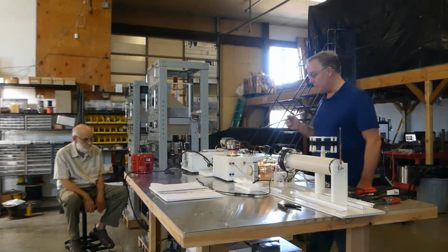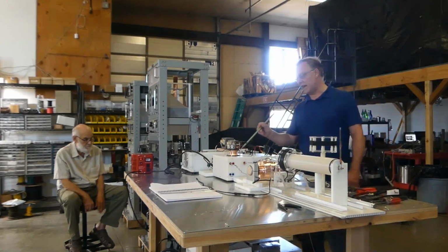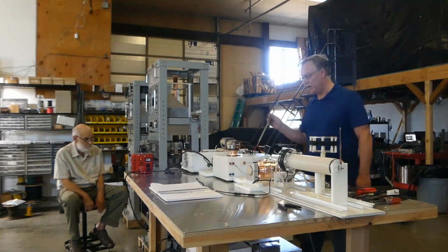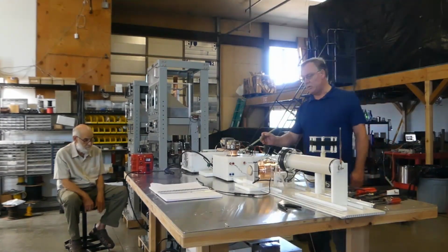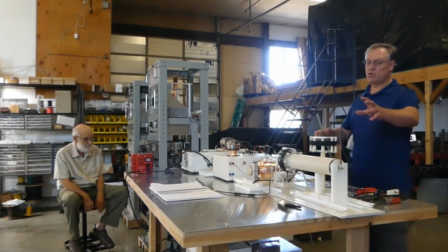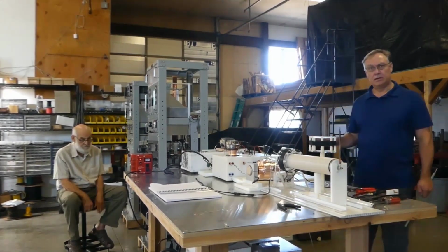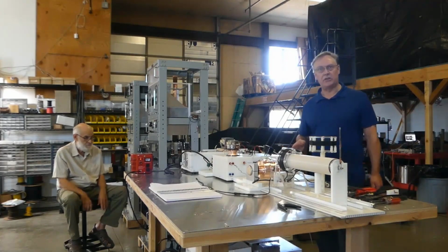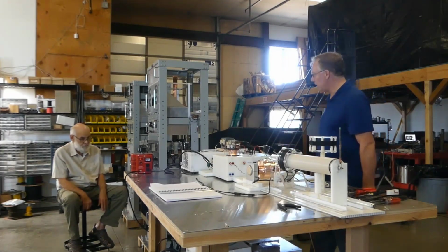And we noticed that because the fan, which actually does the cooling here, is connected to a small DC switch mode power supply, which is located not that far from the anode. The anode is buried down inside this box here. And what we noticed is that when we turned it on and we couldn't strike the arc, the fan stopped. So the fan stopped turning, and when we turned off the high voltage, the fan started again. So that was rather strange. Eric, do you want to go into more detail about why that is?